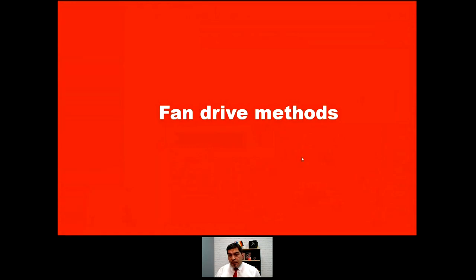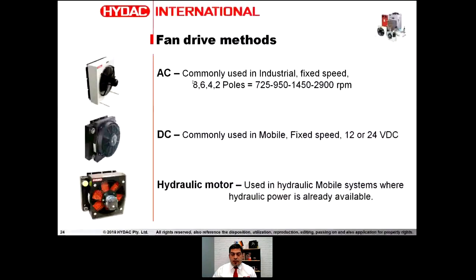There are three main fan drive methods: AC, DC, and hydraulic motor. AC — alternating current — is the standard electric motor, commonly used in industrial applications at fixed speed: eight-pole, six-pole, four-pole, or two-pole, corresponding to 725, 950, 1450, or 2900 RPM. DC is more commonly used in mobile applications, also at fixed speed, at 12 or 24 volts DC.